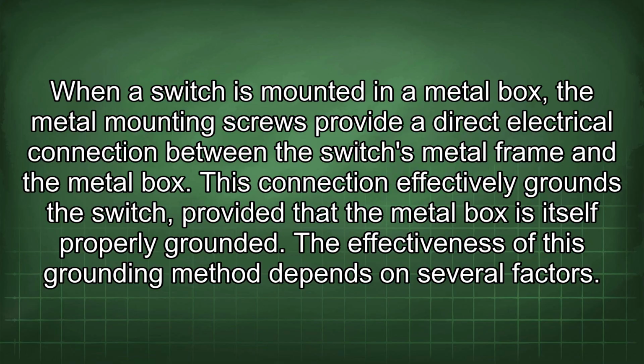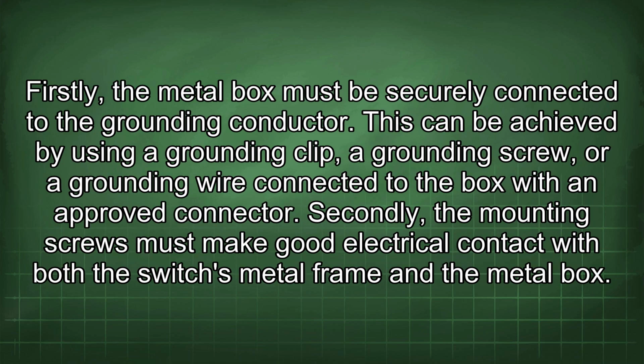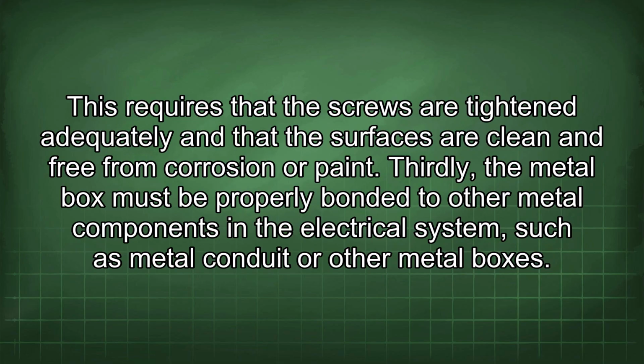The effectiveness of this grounding method depends on several factors. Firstly, the metal box must be securely connected to the grounding conductor. This can be achieved by using a grounding clip, a grounding screw, or a grounding wire connected to the box with an approved connector. Secondly, the mounting screws must make good electrical contact with both the switch's metal frame and the metal box. This requires that the screws are tightened adequately and that the surfaces are clean and free from corrosion or paint. Thirdly, the metal box must be properly bonded to other metal components in the electrical system, such as metal conduit or other metal boxes.